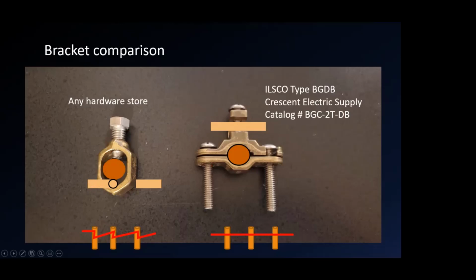It has to come to that rod, go down, and ordinarily, if it was just grounding a service panel, it would stop there. But if you're going to keep going on, you come down and go up to the next rod, and down and up to the next rod. You end up with these sharp bends, which is not a good idea—that's not something you want on your grounding rod.